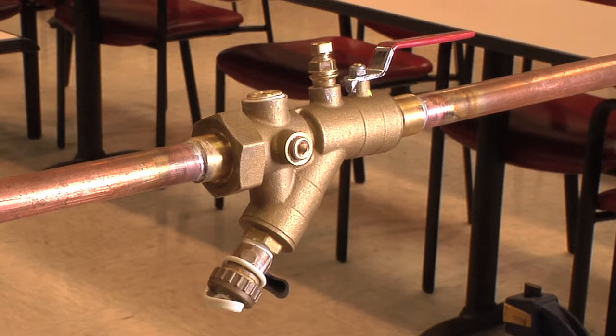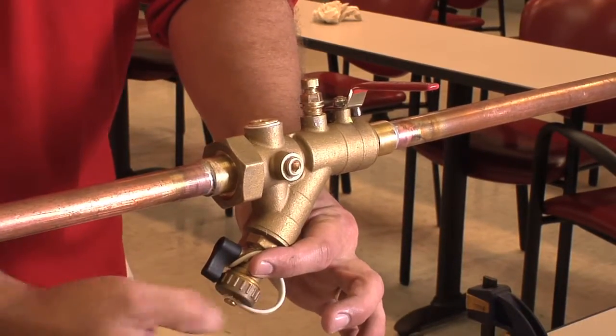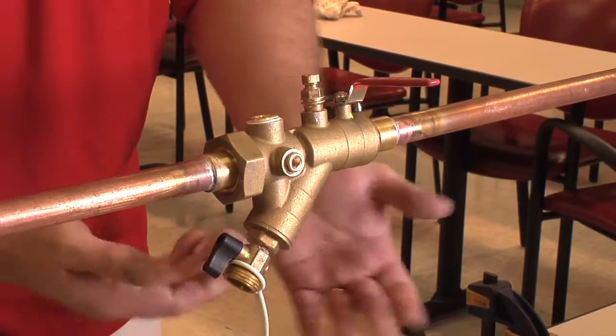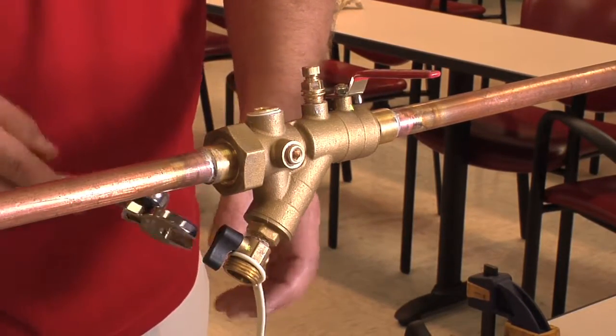We'll begin our procedure by isolating and draining the Y-strainer valve completely. Once the valve is open to atmosphere and it's at a safe handling temperature of 100 degrees Fahrenheit or less, we will want to begin the internal strainer removal process.